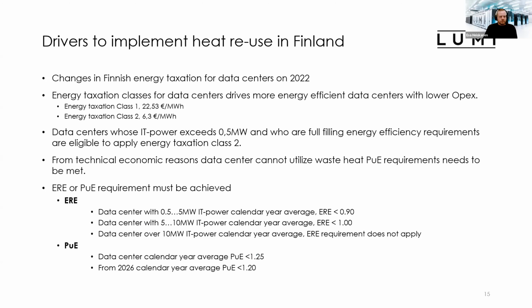Also in Finland we have some drivers to implement heat reuse. So actually in the Finnish energy taxation a change was made at the beginning of 2022 so that data centers that are fulfilling these energy efficiency requirements are able to apply for this lower energy taxation class, which is much cheaper in operational costs than running the data center with class 1. This used to have a limit that only data centers whose average IT power per year was over 5 megawatt were able to apply for this lower energy taxation before 2022, before this change was made. But now even the smaller data centers that are exceeding 0.5 megawatt of IT load, and are fulfilling these energy efficiency requirements, are able to apply for energy taxation class 2.